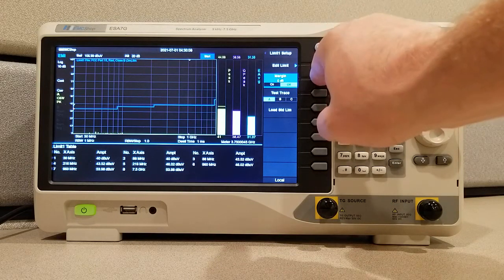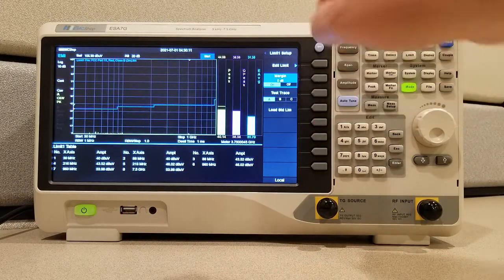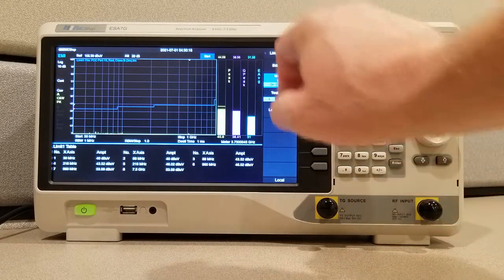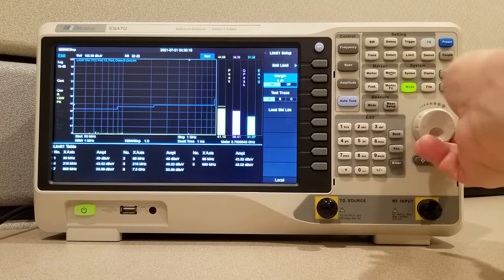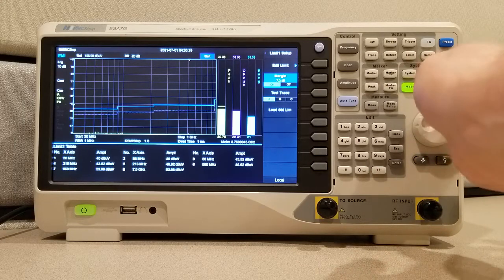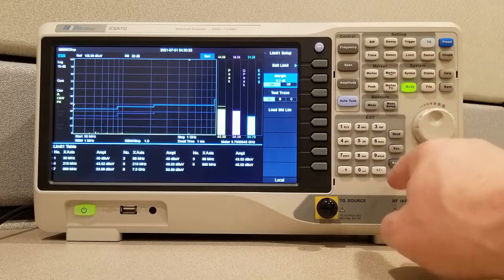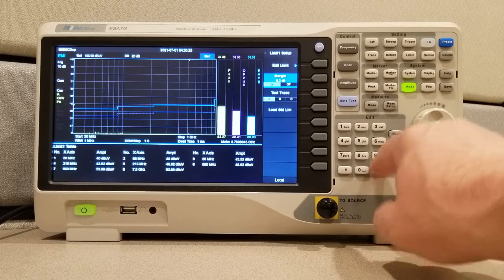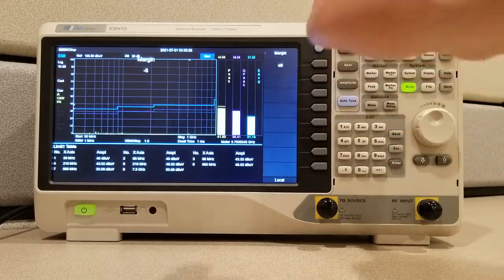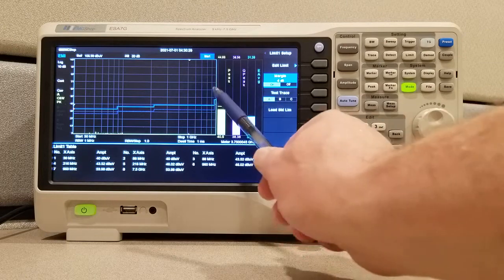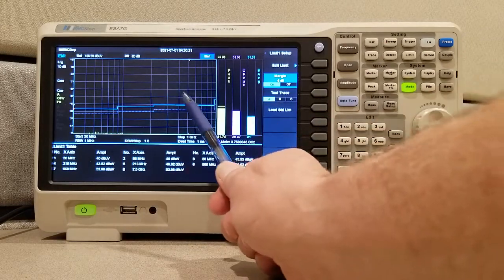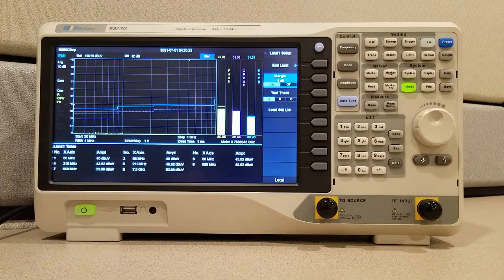And we want to put a 6dB margin below that limit. So we push the margin button to turn it on. And you could either use the dial to lower that line down to wherever you'd like it. Or you use the keypad, push negative 6dB. And you could see the margin line is 6dB below the limit line.